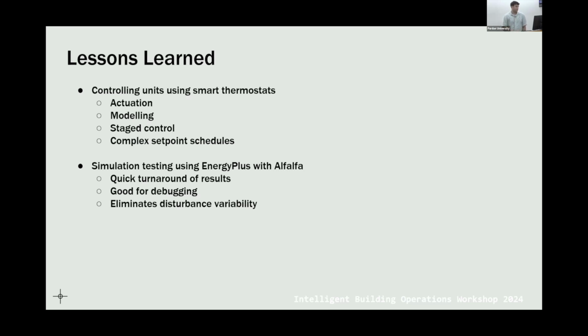When you actuate the units using temperature set points, you kind of lose the nuance of staging, because it's difficult to know exactly how the internal control of the rooftop unit responds to these deadbands. You might be able to say, okay, at 1.2 degrees it will initiate stage 1 cooling, but it's not reliable. So usually you have to overshoot it, and it becomes effectively a single-stage unit when you do it that way.